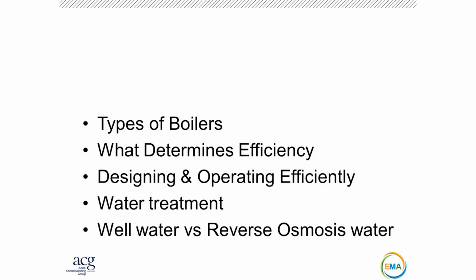The last line that's on here, though, is actually fairly important. So well water versus reverse osmosis, and this could say soft water or DI water or anything. We all come from different parts of the country, and depending on where you're from, the water source is very different. And here in Texas, the water's horrible. In West Texas, it's not as bad here. You go to Chicago, they pull out of Lake Michigan every day. The water's always the same. It's good water. We know how to take care of that pretty consistently. Know your water source. Make sure you pick the right boiler for what kind of water you're pulling in. Reverse osmosis is great, but it's extremely corrosive. So I'm okay putting that on stainless steel, but probably not black pipe, copper, things like that. So always know what you're working with as far as your water source, as a good pre-treatment portion of this.